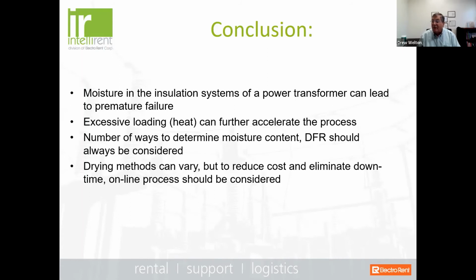There's a number of different ways to determine moisture content, but I would recommend that DFR is something you'd want to consider if you truly want to know how much moisture is in that insulation. And drying methods can certainly vary, but if you want to reduce cost and eliminate downtime on your transformer itself, this online process should be considered.